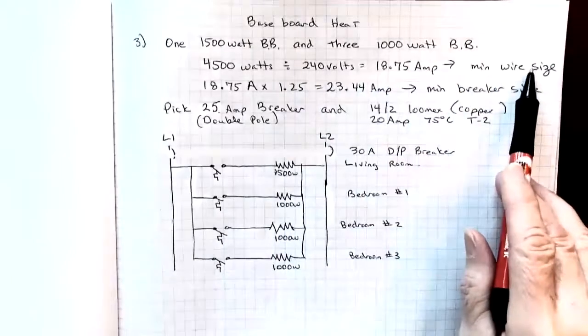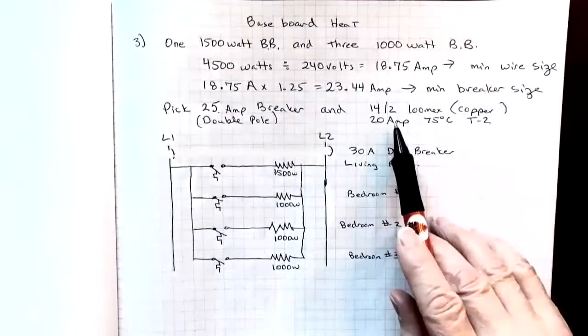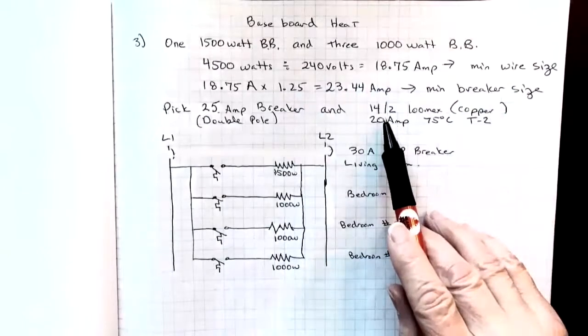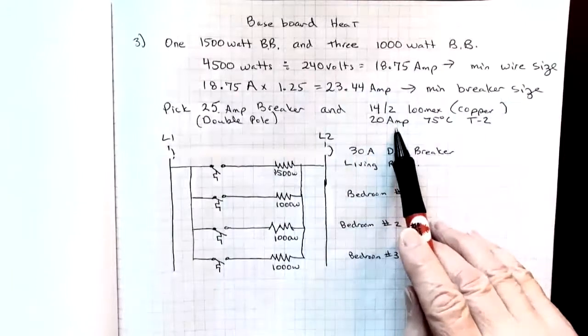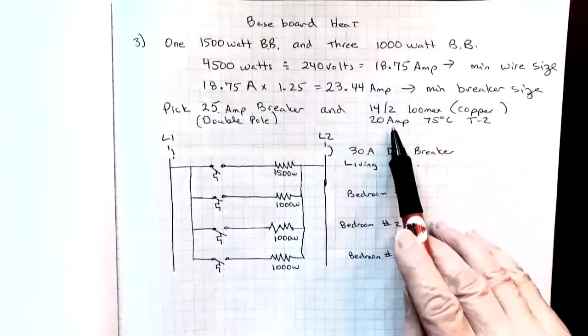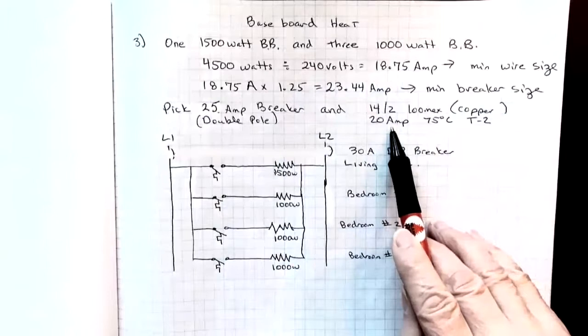Remember, the wire can be smaller than the breaker. So again, in table two, a 14-2 wire can easily carry that 18.75 because it's rated at 20 amps.